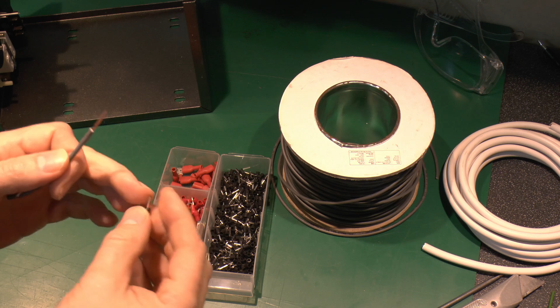Now for the end of the wire we're going to need some of these pin terminals, or ferrules - they go over the wire and get crimped down so we don't have any stray strands flapping out. That's a bit long, so just stripping it for a random length. For the others, we've got these rings, which again just crimp onto the end of the wire. And for the press-on connectors, these crimp on the end as well, so various different styles of connectors here.